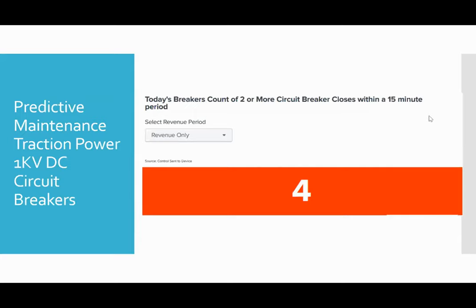When you shift into creating algorithms to prevent outages, we took a close look at our traction power 1 kV DC circuit breakers. Every night we shut down our entire traction power grid, which is basically a giant power plant with substations and track and electrical along the entire trackway. We shut everything down for safety during maintenance, what we call the blanket, and then we re-energize the plant afterward.